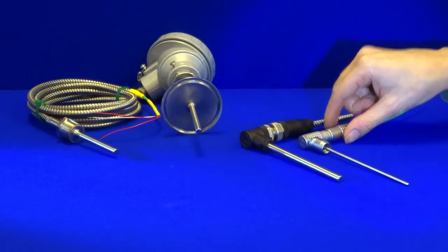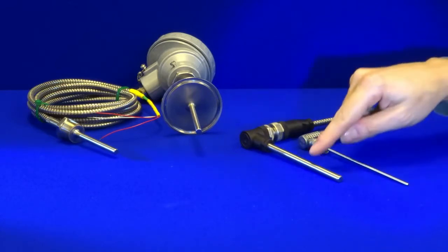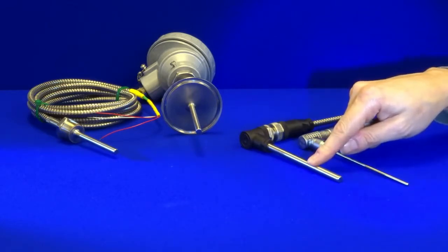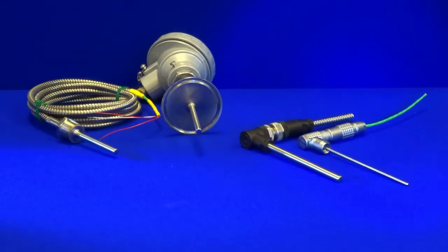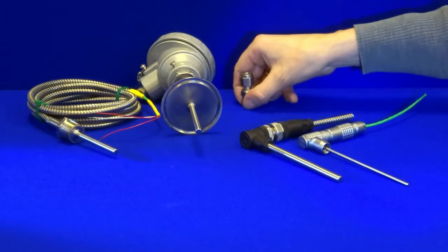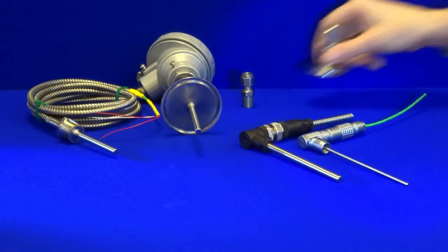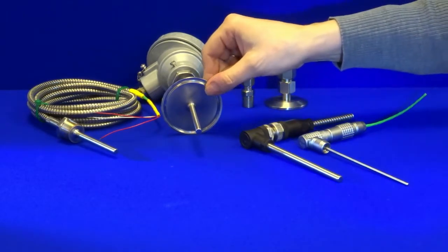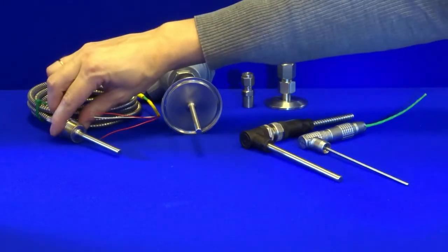The sheath diameters are 3mm and up to 1/4 inch diameter, and to any length, because we'll custom build to your specification. Mounting is either in the form of a compression fitting or a welded process fitting for a more permanent fixture.